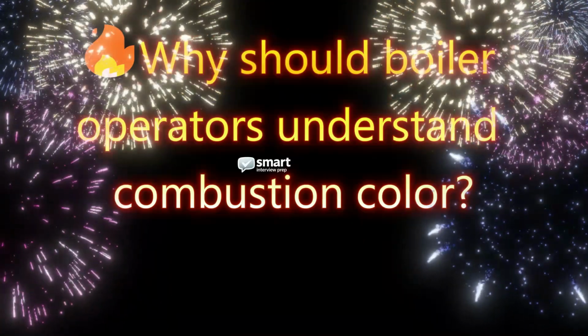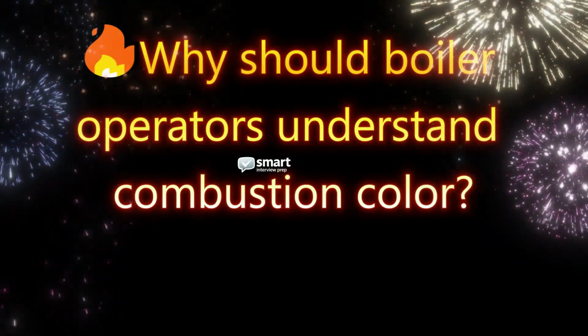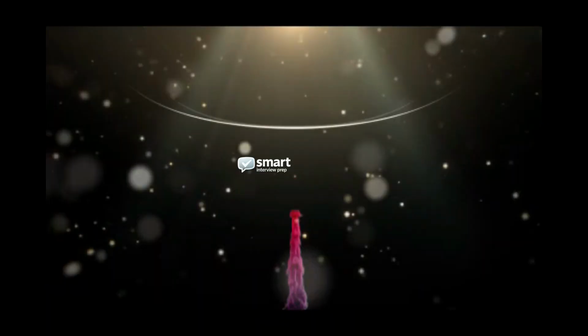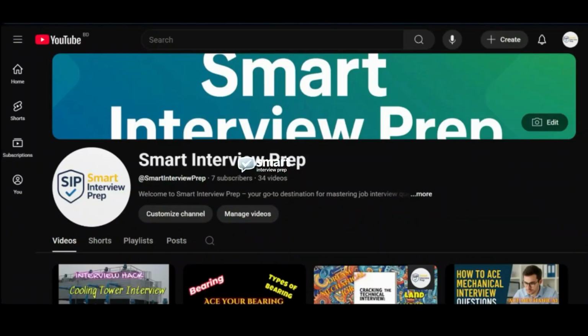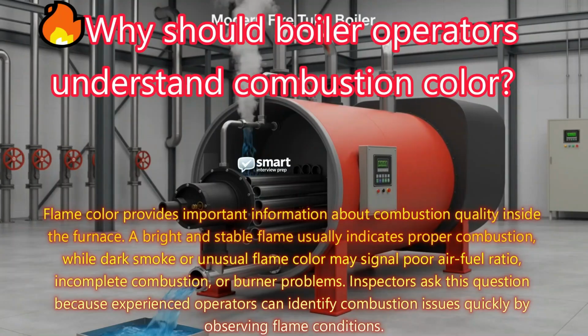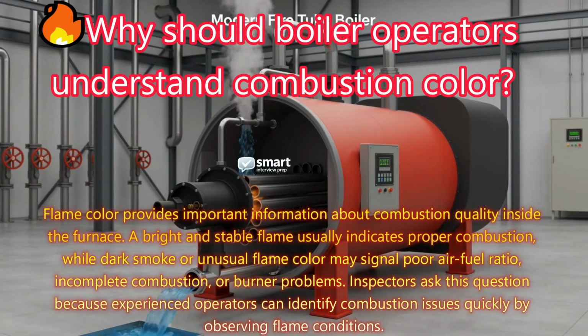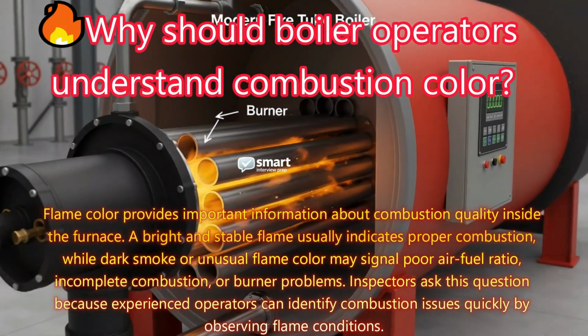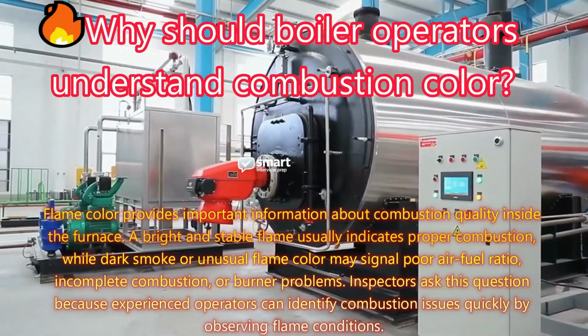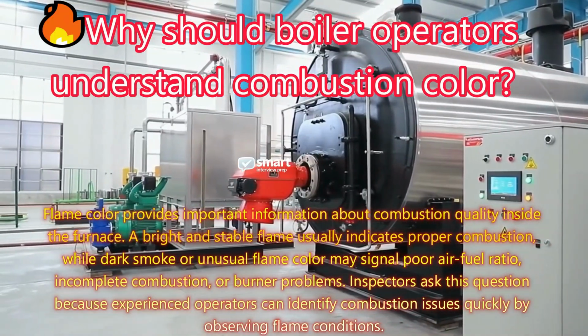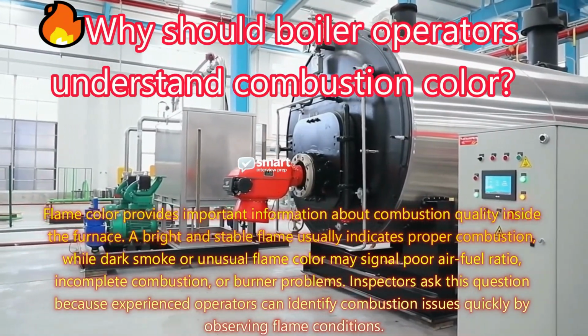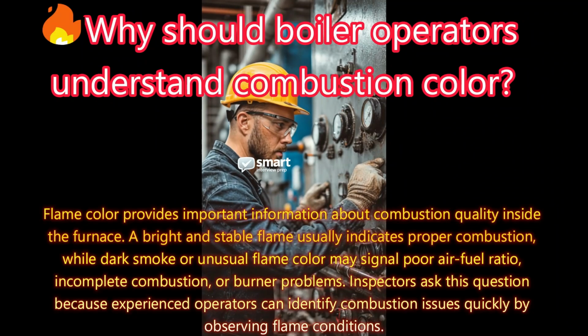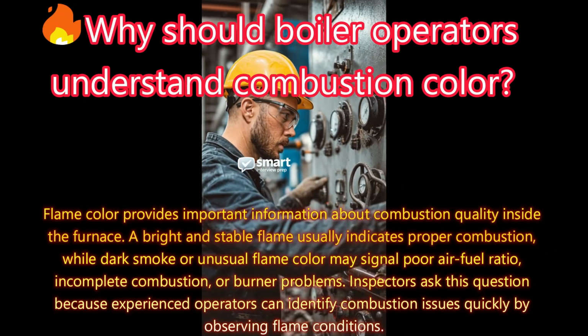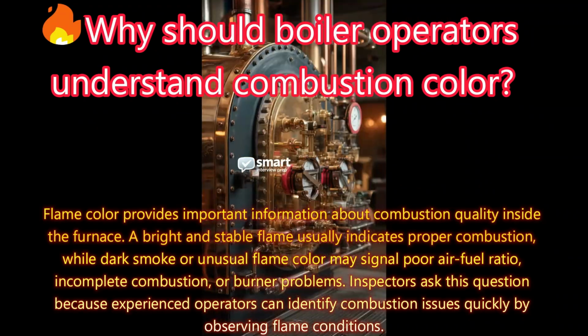Let's start. Why should boiler operators understand combustion color? Answer. Flame color provides important information about combustion quality inside the furnace. A bright and stable flame usually indicates proper combustion, while dark, smoky or unusual flame color may signal poor air-fuel ratio, incomplete combustion, or burner problems.